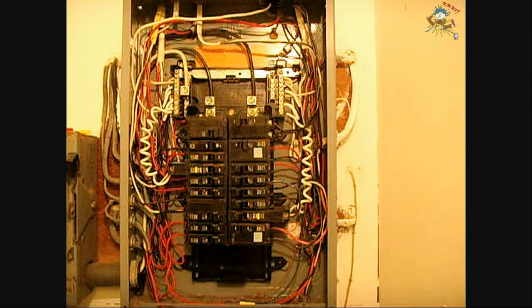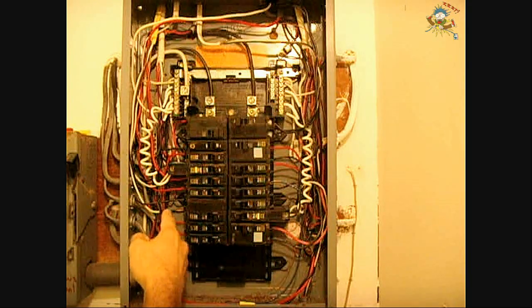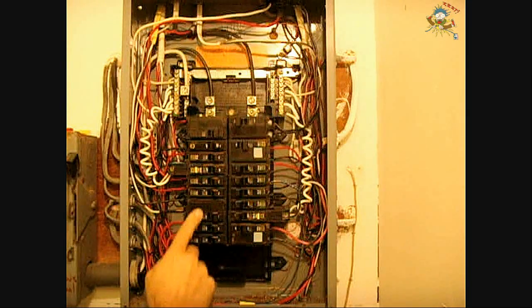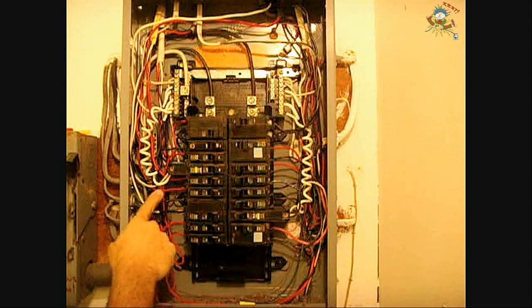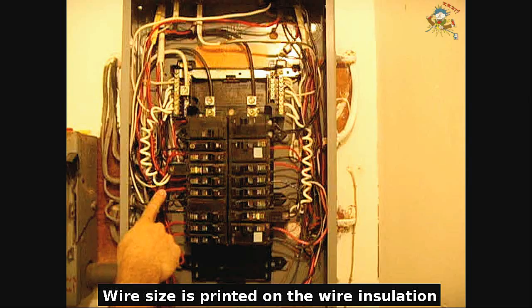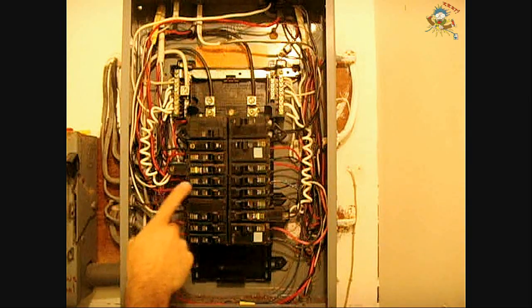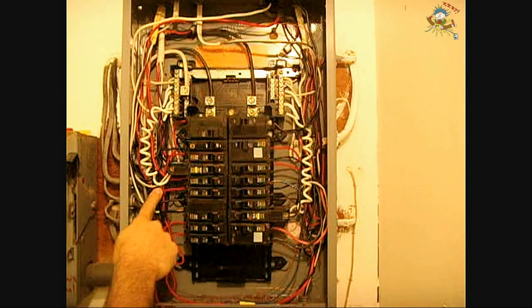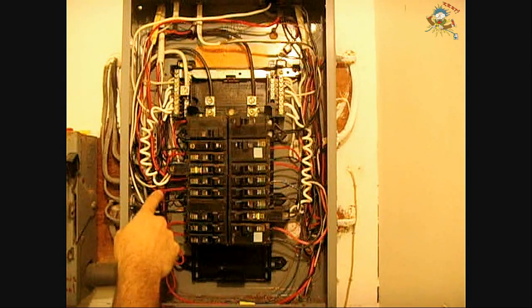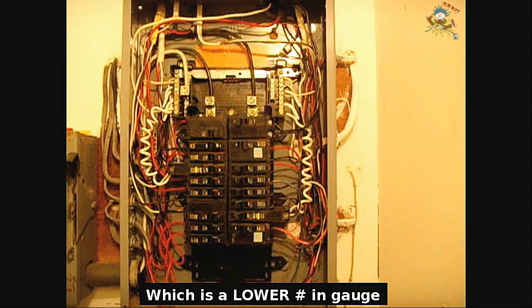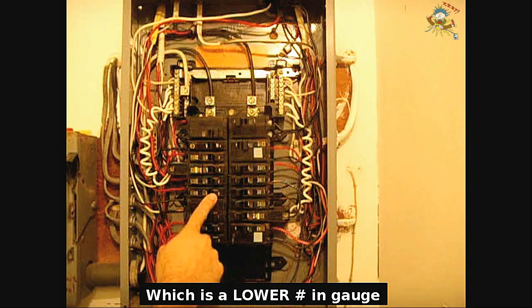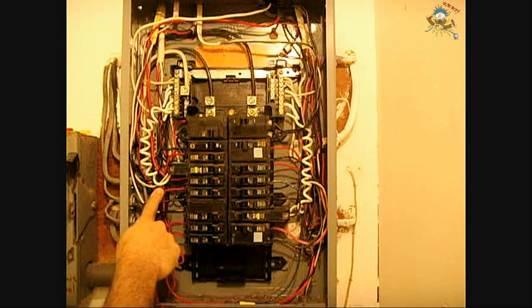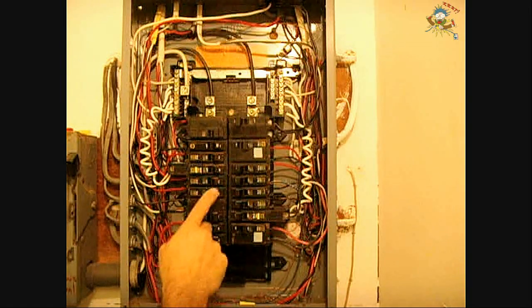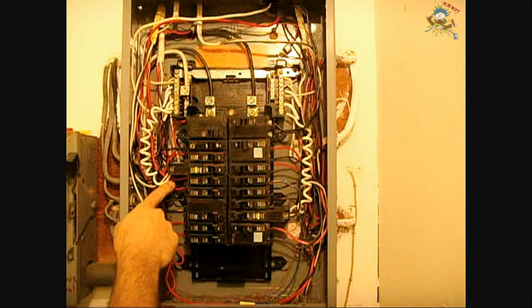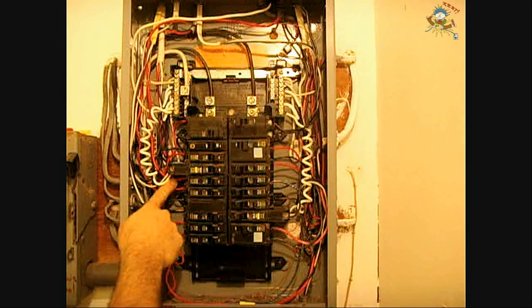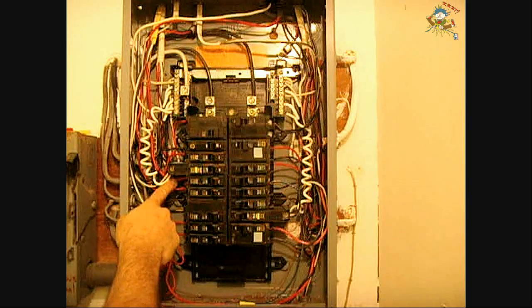Now the first thing you want to do when you look at the panels, you want to observe the wire sizes in relation to the current rating of the breaker. If you have a 15 amp breaker, you want to make sure that the wire attached to that breaker, whether it's stranded copper or solid copper, is going to be 14 gauge copper. If you're using aluminum, aluminum has higher resistance than copper. You're going to want to use the next wire size thicker to compensate for the difference in resistance. For a 15 amp breaker, instead of using 14 gauge copper, you would be using 12 gauge aluminum. Now if the circuit breaker is rated for 20 amps, you're going to want to make sure that the wire is a 12 gauge solid copper or stranded wire, or a 10 gauge aluminum.